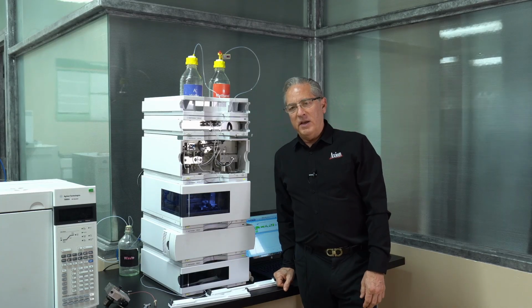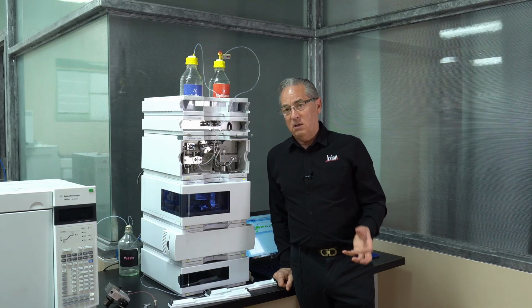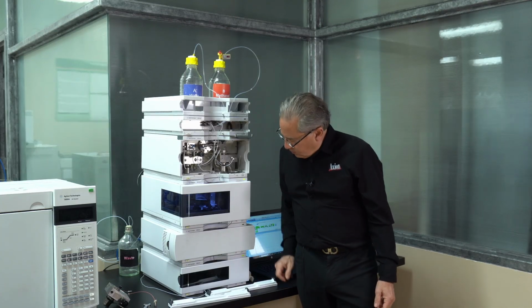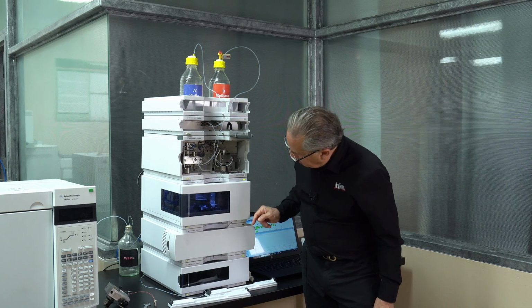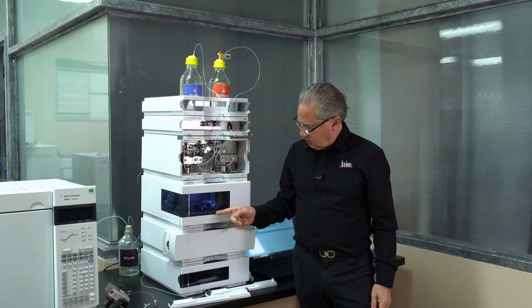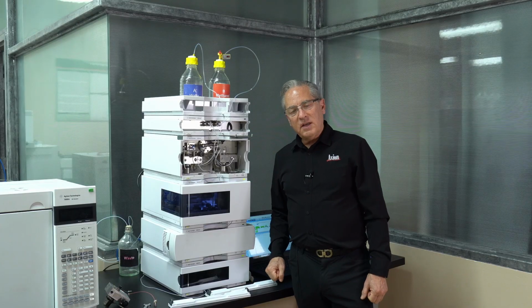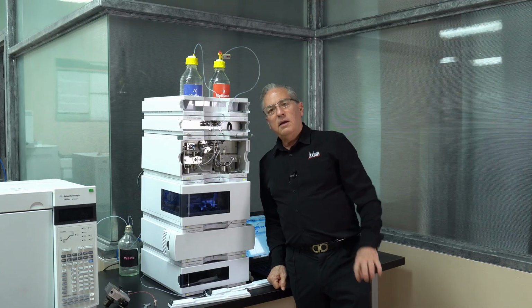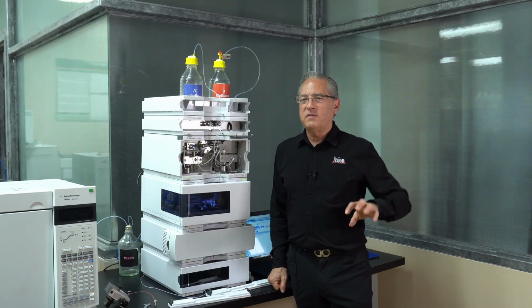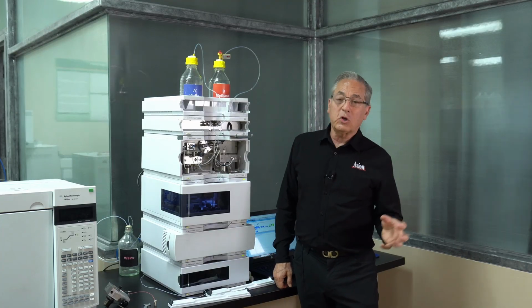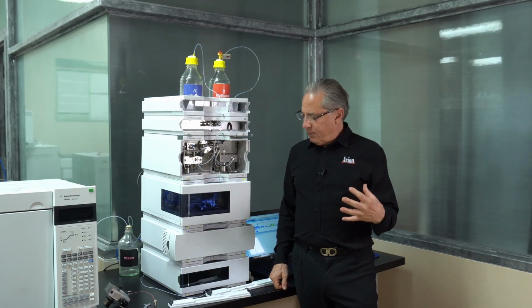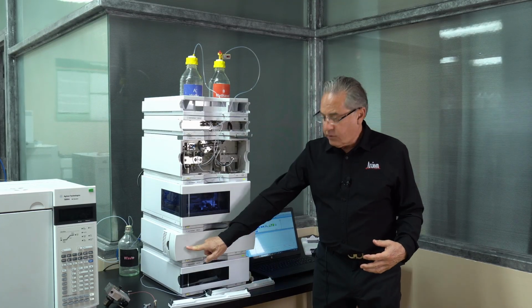And as we hear it making noise, that first noise was the valve switching to the bypass mode. So now you'll probably see the needle moving around, and what it's going to do is it moves to the sample, draws in sample, and then that last little sound you heard, that was the valve rotating back into what's called main pass. So that picked up the sample. The sample is now traveling through the column.